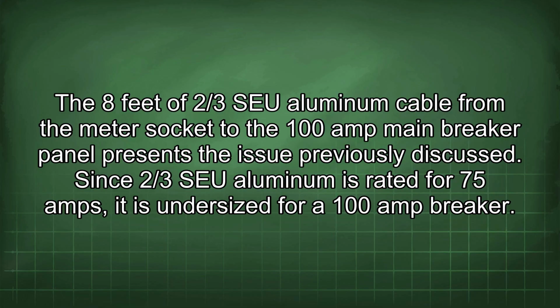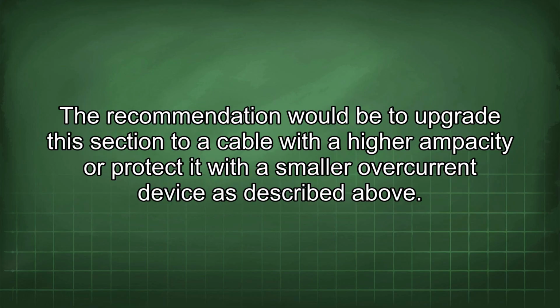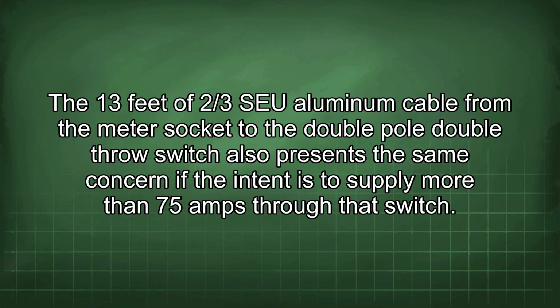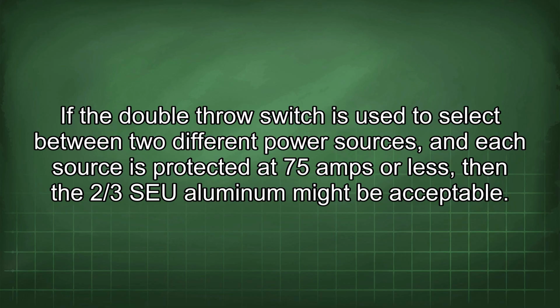Since 2/3 SEU aluminum is rated for 75 amps, it is undersized for a 100 amp breaker. The recommendation would be to upgrade this section to a cable with a higher ampacity or protect it with a smaller overcurrent device as described above. The 13 feet of 2/3 SEU aluminum cable from the meter socket to the double pole double throw switch also presents the same concern if the intent is to supply more than 75 amps through the switch. If the double throw switch is used to select between 2 different power sources, and each source is protected at 75 amps or less, then the 2/3 SEU aluminum might be acceptable.